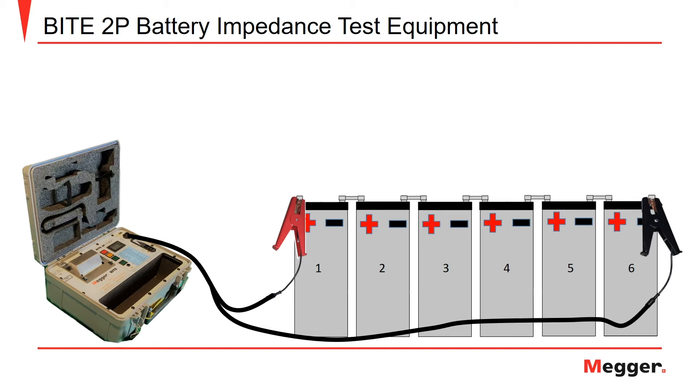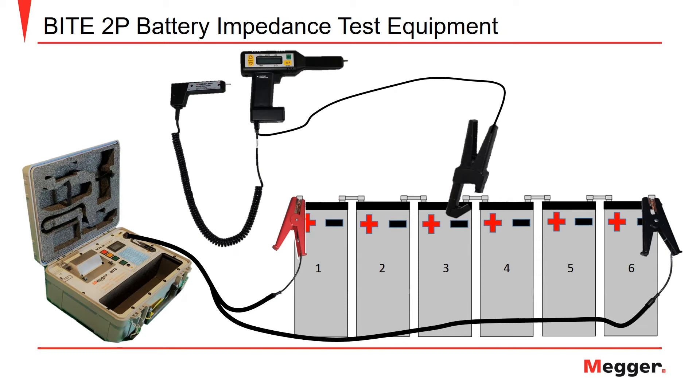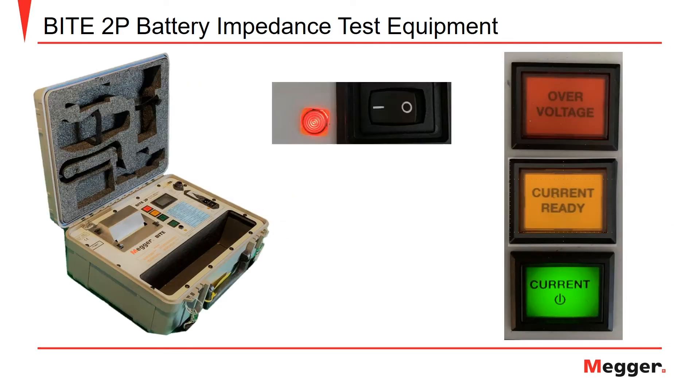Now that we have connected the current injection clamps and the amp clamp, we will talk about how to apply the receiver pistol and potential probe to take measurements across the battery string. The pair of pistol grips are used to take three types of measurements: battery impedance, cell voltage measurements, and intercell strap resistance.